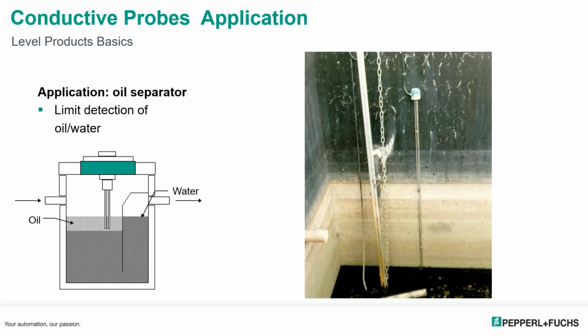A typical application is an oil separator type system. Here we show a conductivity probe in an oil-water mixture. Now, obviously, the oil is going to be floating on the surface of the water. So as this rises, the probe's not going to detect the oil because it has a very low conductivity. But as soon as it reaches the water level, it will detect it. So it detects when the water level gets to below the oil.